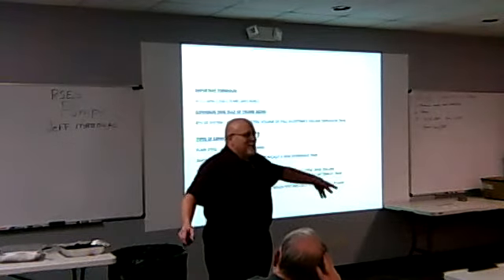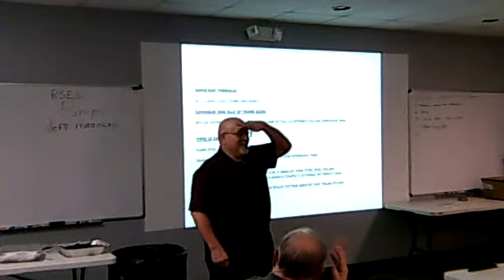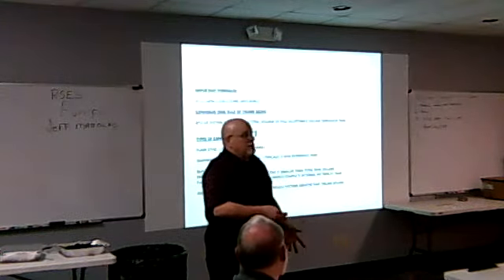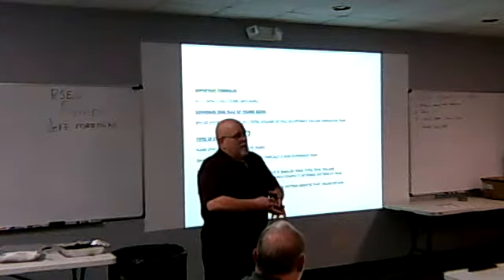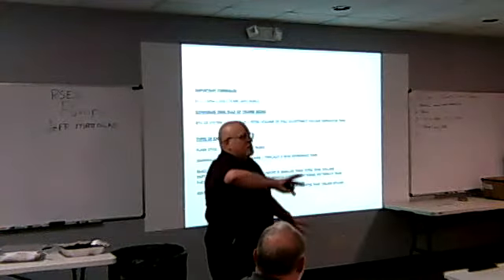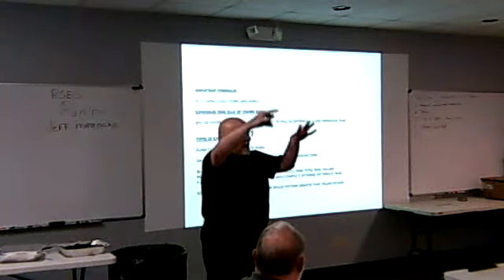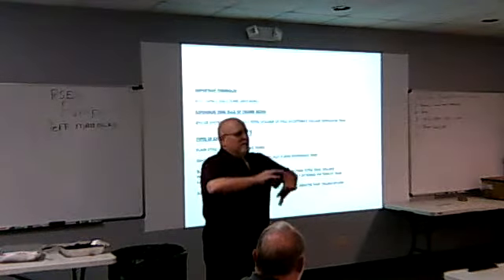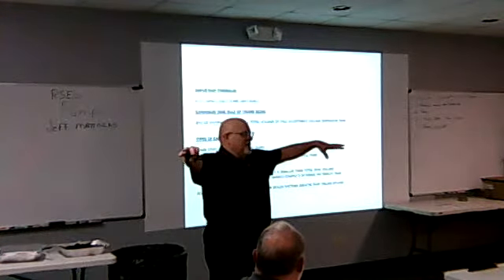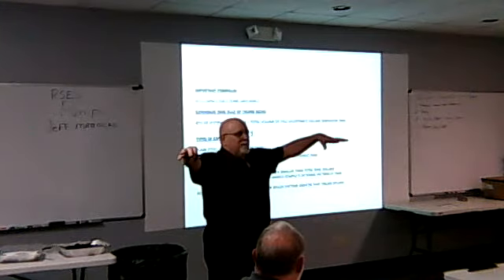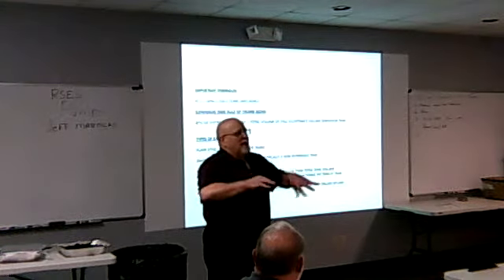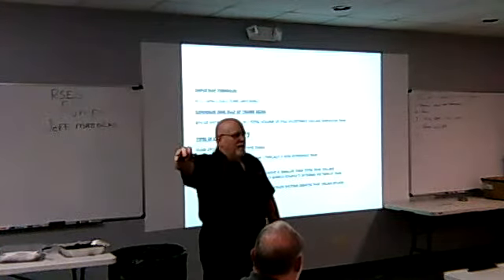We're at 100 pounds. And then when the system backs down in temperature, guess what? The water's going to creep down. That pressure in the tank's going to push the water back in the system. When I get back down to fill pressure, my system's going to be back at fill system pressure, 15 to 20 pounds. But it's okay to let it go up. You don't have an issue until we lift relief valves.